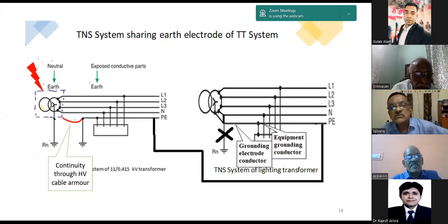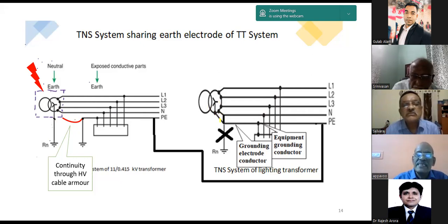This is a lighting transformer. They have a delta star configuration. See, normally in a TN-S AC system, the star point will be connected to an earth electrode first. Then only it will be the PE, that is protective earth. Earthing conductors will be terminated here finally. But what was done in that site was, they have just looped this and avoided this earth electrode.